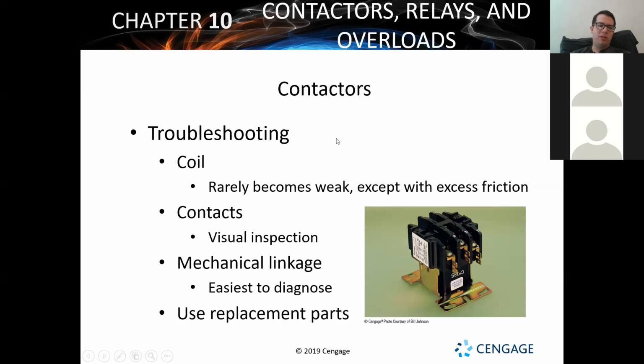Again, with coils, there are usually a few things going on. Most of the time, if they're getting voltage, they're going to work. No doubt about it. If it gets voltage, that coil is going to energize. It's going to pull down that armature, and it's going to let power pass right through it. The problem with the coil that commonly occurs, that I've seen, is that coils become open. When it's a bad coil, it's because it's an open coil or a shorted coil, which you can check if you turn the power off and look for resistance.